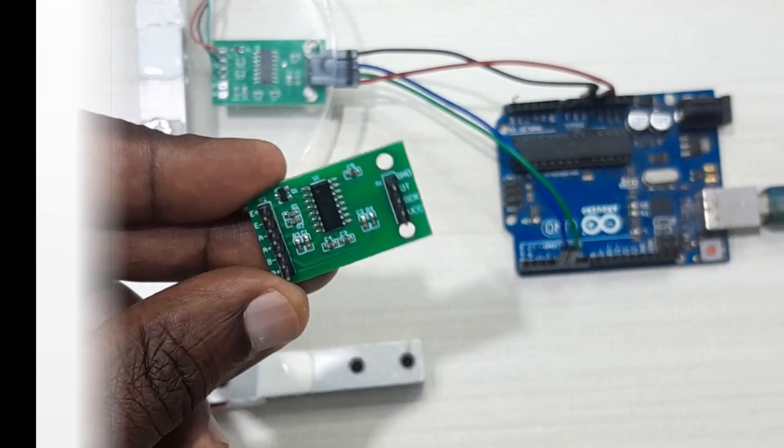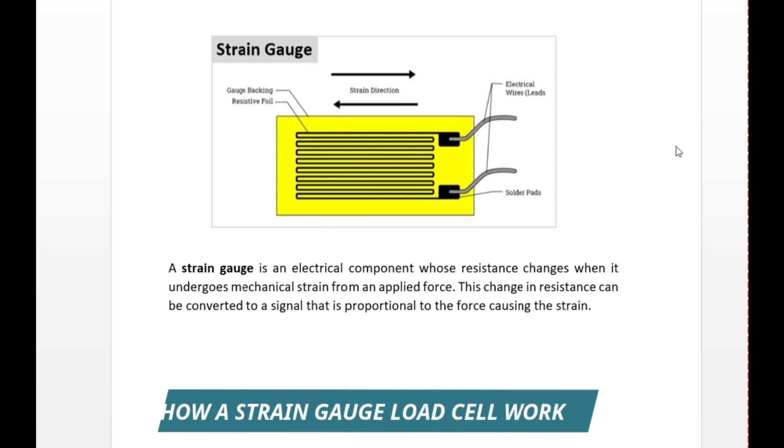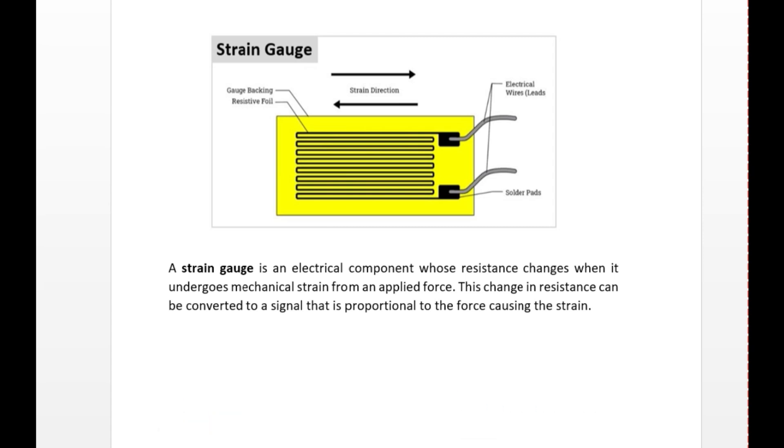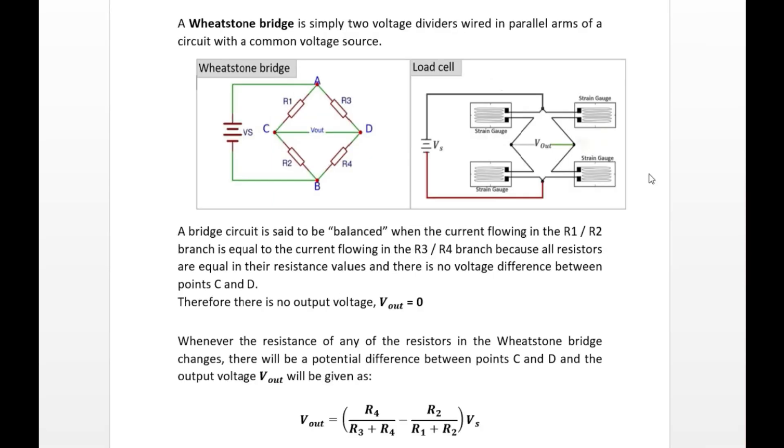Before proceeding, let's first look at how this sensor works and how we can calibrate it. We are looking at a 4-wire bar-type strain gauge load cell. This cell uses the change in resistance to measure a force being applied. That change in resistance is measured using the strain gauge. It is simply an electrical component whose resistance changes when it undergoes mechanical strain from an applied force. The strain gauge consists of a thin metal conductor foil attached to a flexible backing material known as the carrier. Electrical leads are soldered to the foil allowing current to flow through the strain gauge. So whenever the surface of this gauge undergoes tension or compression forces, the strain gauge deforms accordingly, leading to variation in electrical resistance that corresponds to the changes in the surface dimensions. This is the major component responsible for measurement of resistance in the load cell.